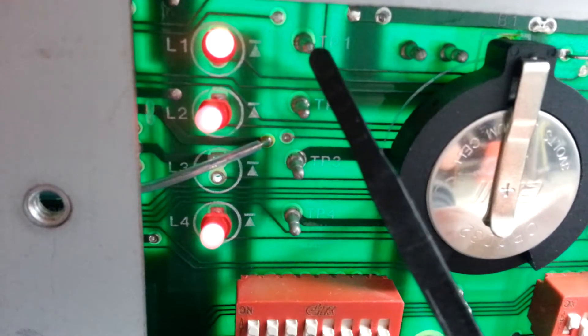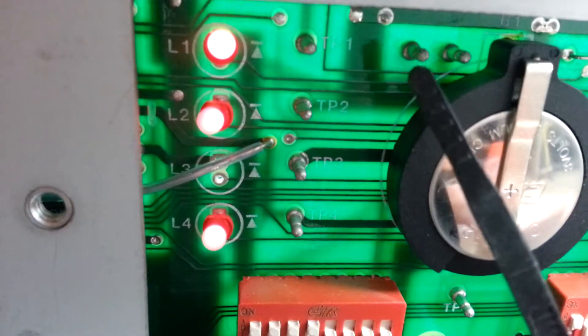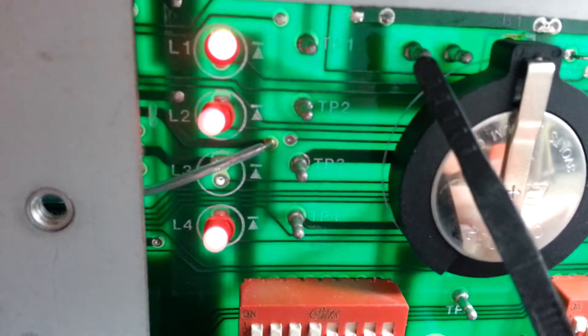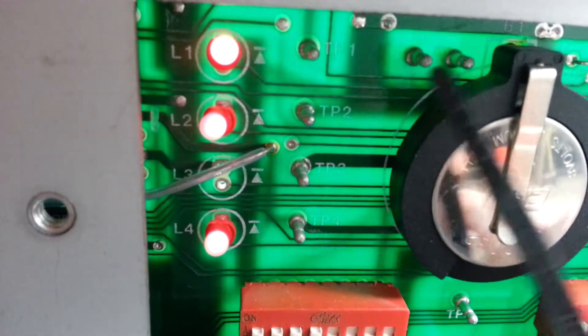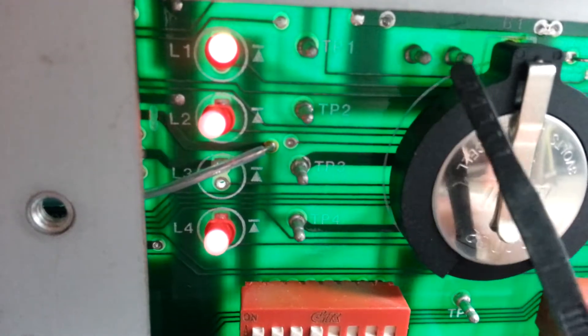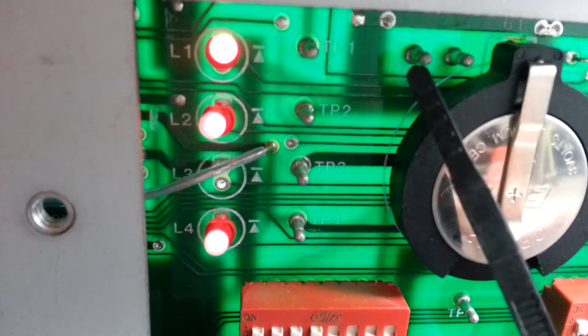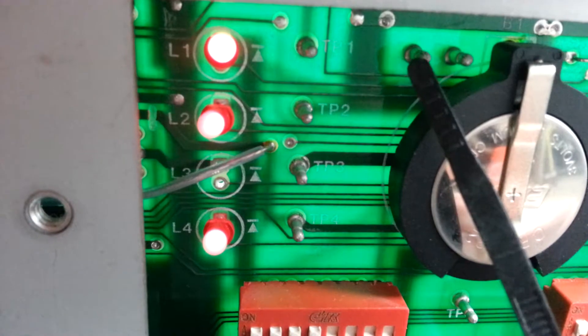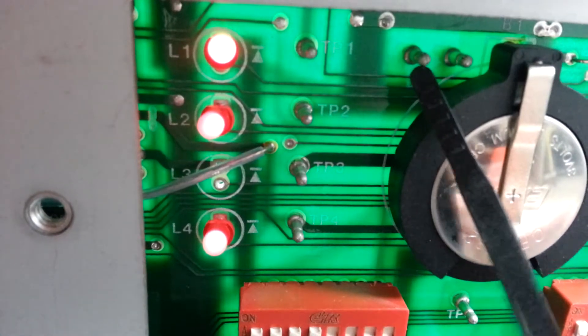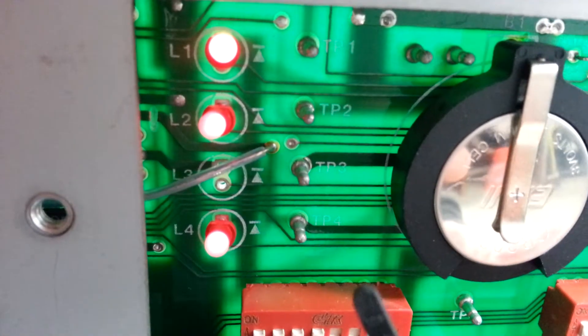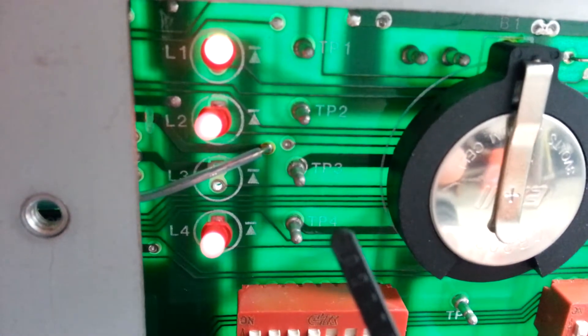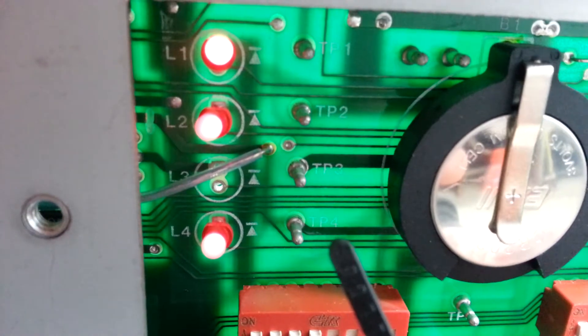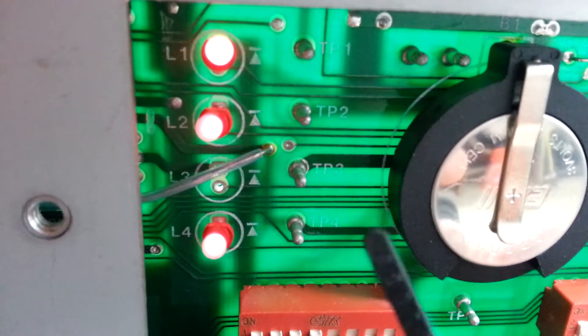TP1 is where you measure your 5 volts. Over on the early model, you'll have two of these test points at about 11 o'clock where the battery is at. The outer one is your ground reference, so you're going to have your ground reference to TP1 for measuring your voltage, and you should be approximately 5.2 to 5.24 volts DC.